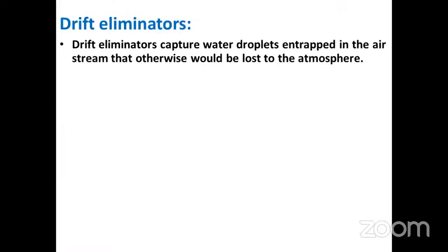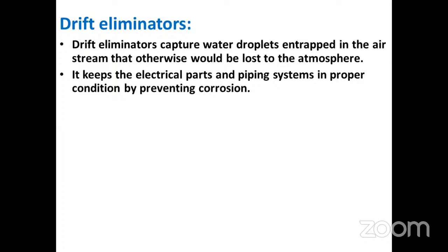Drift eliminators. Drift eliminators are provided to capture water droplets entrapped in the air stream that otherwise would be lost into the atmosphere. When the air is going upward, it captures the water particles and takes them away with it to the atmosphere. Then we will be losing a huge quantity of water. So we need to have some mechanical arrangement so that while going through the drift eliminators, the air gets condensed and the water drops down due to gravity, and the air leaves the drift eliminators with a reduced quantity of water in it.